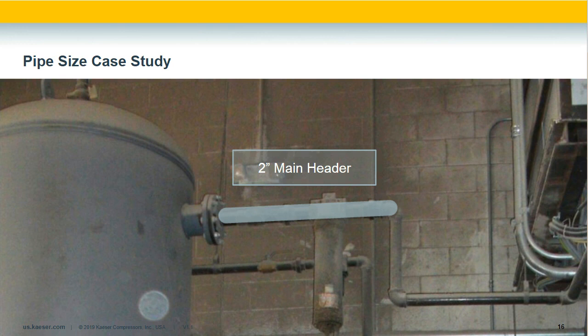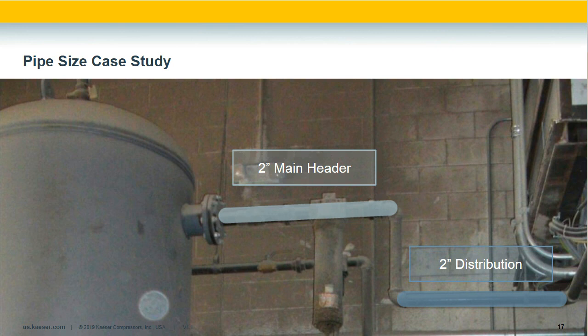The actual system had approximately 1,300 CFM on average during peak flowing through a 2-inch main header in the compressor room — that's where most of the pressure drop occurred. The distribution piping was also 2-inch. The majority of the pressure drop happened because pipe size didn't meet current demand, resulting in a 10% to 15% energy increase. Piping plays a significant role in system performance and may stay in place long after compressors are replaced — potentially 50 years.